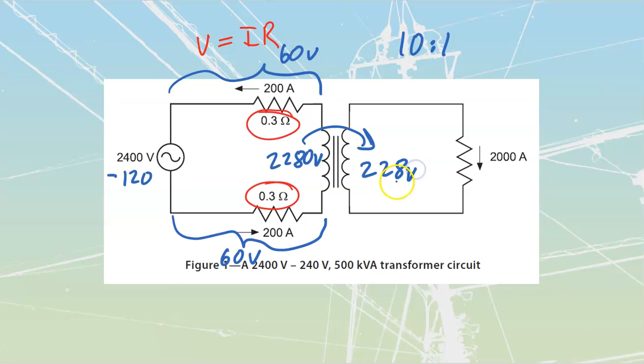That is not what we want to have out—we want 240 out. Instead we're ending up at 228, so we've had a bit of a voltage drop happen inside of here. To compensate, it would be nice to adjust what we have on this transformer—to somehow change the turns ratio inside of here. Instead of going down from 10-to-1, we'd use a smaller ratio, so we wouldn't end up quite as far down.